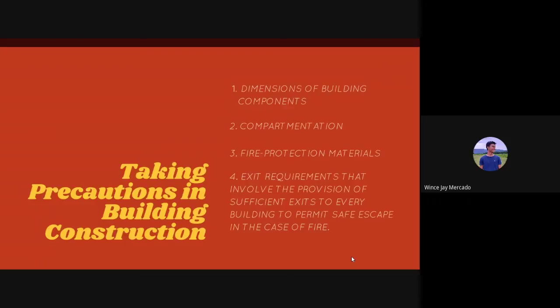Each mezzanine floor used for other than storage purposes, if greater in area than 185 square meters or more than 18 meters in any dimension, dapat merong at least 2 stairways to an adjacent floor. Every story na may occupant load na 500 to 999, dapat magkaroon ng 3 exits. Sa story naman na mayroong occupant load na 1,000 pataas, dapat magkaroon ng kahit 4 exits man lang.